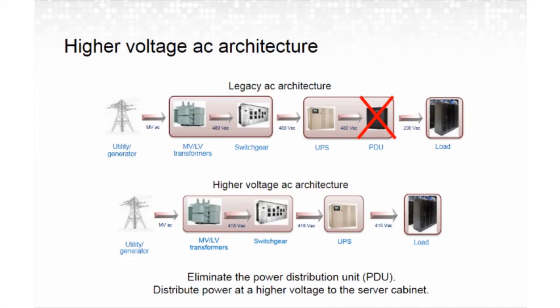There are some downfalls, as Rich had talked about. Transformers do create impedance, which does cut down on the fault current. So by eliminating that transformer, you do create higher fault current. So you just have to make sure, when you're doing that, that you look at how you adjust the system and do a coordination study and short circuit study so you can understand the currents that you're talking about.